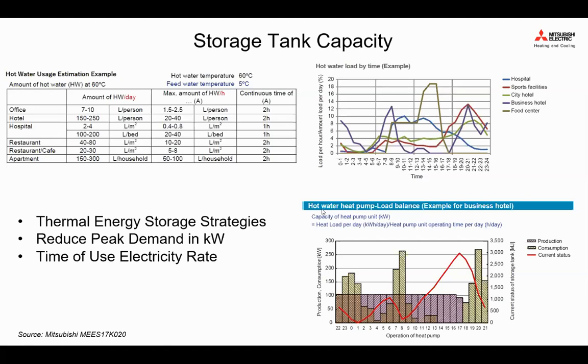So you may be able to utilize some energy conservation strategy, such as load shifting or load leveling, to reduce your peak demand in kilowatts. If you know you're going to use the most hot water from 7 to 9 o'clock, and in Ontario we're using time-of-use electricity, then maybe you can spend the off-peak hours to create hot water and store it in the hot water tank, and then reduce your peak load.